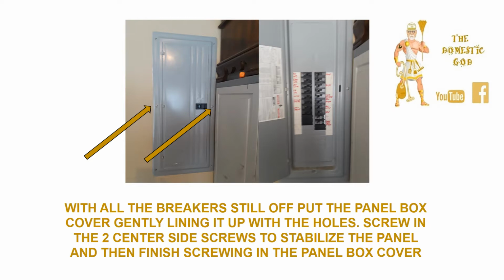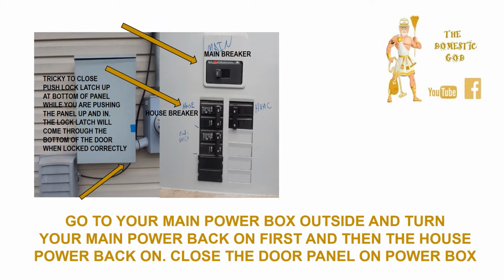With all the breakers still off, put the panel box cover on gently, lining it up with the holes. Screw in the 2 center side screws first to stabilize the panel, and then finish screwing in the panel box cover on the outer edges. Now go to your main power box outside and turn your main power back on first, and then the house power back on. Close the door panel on the power box.